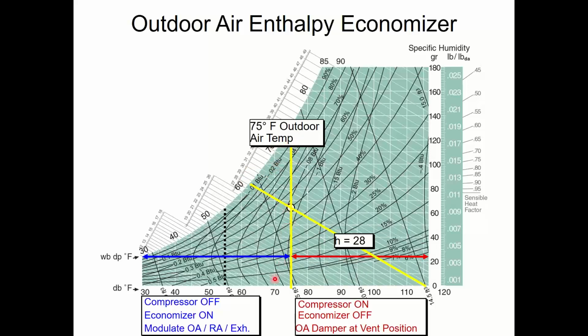I did have to move my line from the 70 to the 75 number, so I get to take these days as economizer days, which is great, but I don't have to take these humid days. Trade them off. That's why you're going to want an enthalpy economizer.